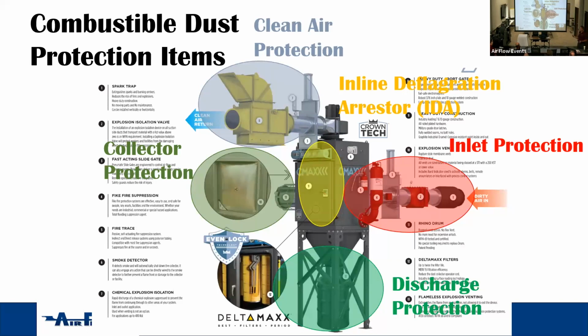And what makes that important is when you hear about a collector explosion or a collector fire, most of the devastation that occurs, if there's any injuries or any life lost, it's not the initial explosion that gets anything. Usually these are outside, usually they're located in a space that's fine and nobody's working directly around them. It's that explosion that occurs here, and if there's no protection device going back into the building, it's that secondary explosion that occurs. So most facilities that have dust in them will have dust located on the bottom of the trusses, will have dust located on ductwork, conduit, whatever is in there. What happens in an explosion is the flame ball goes through first. So the flame ball goes into the building first.